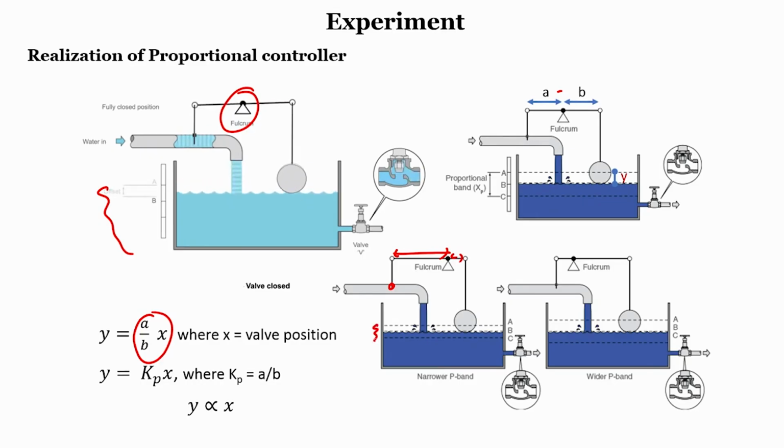When the flow keeps on increasing, you can see a sudden close, a sudden stop of your input. So this error band entirely depends upon the gain, where exactly you are using the fulcrum. Whereas if A is smaller and B is higher, the gain is very small, it takes a longer duration, which means the proportionality band will be even higher.